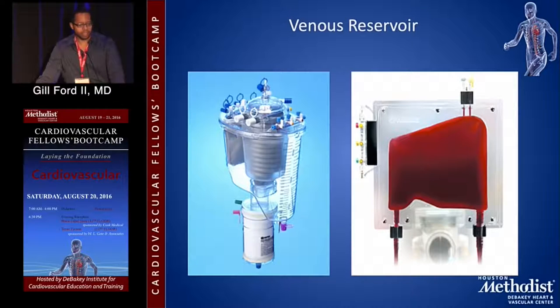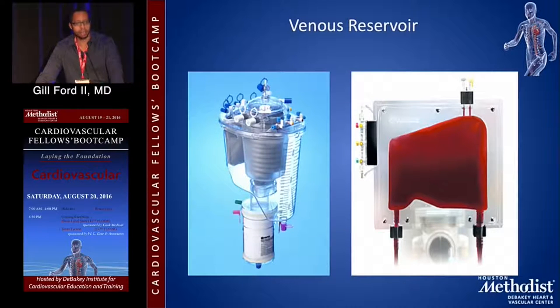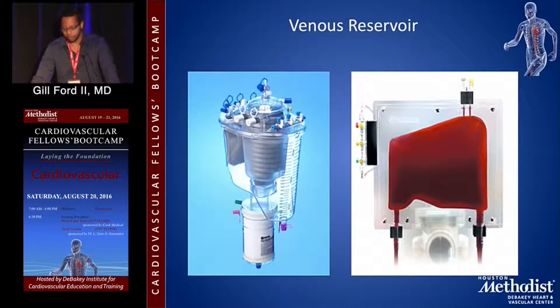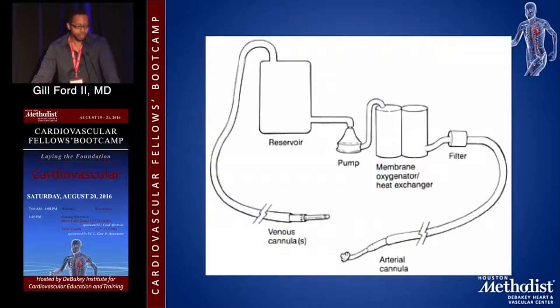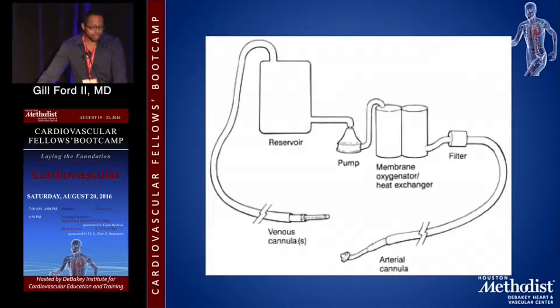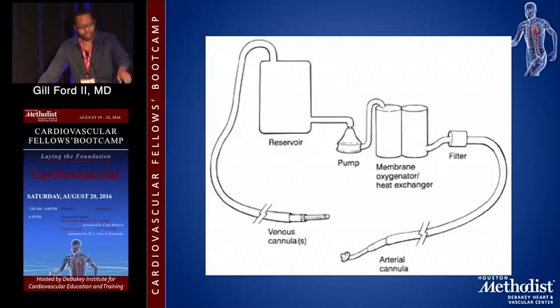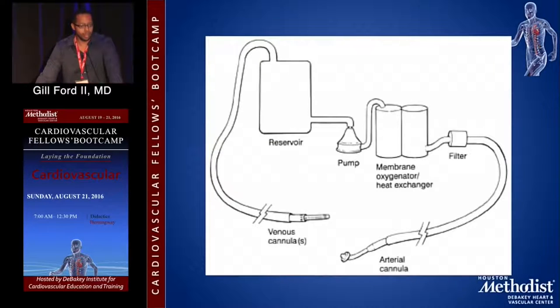The hard shell reservoir has all the ports and doesn't require external reservoirs. The soft shell offers a safety benefit: if you drain it down by mistake, it will collapse and prevent you from pumping air to the patient. The circuit has cannulas inserted into the patient's heart, connected by tubing back to your reservoir. Follow the flow: through your pump, oxygenator, filter, and then right back into the patient.